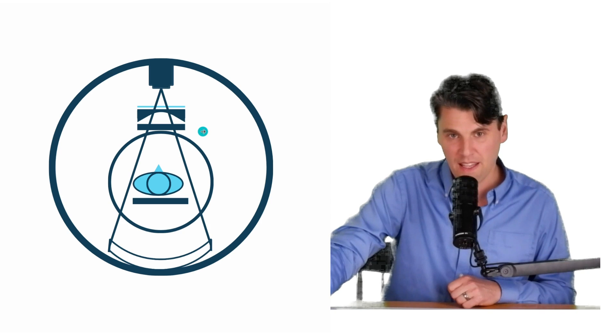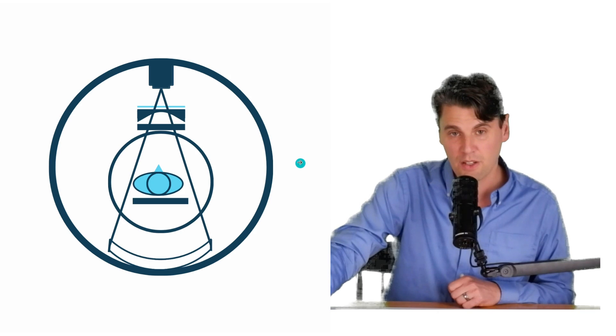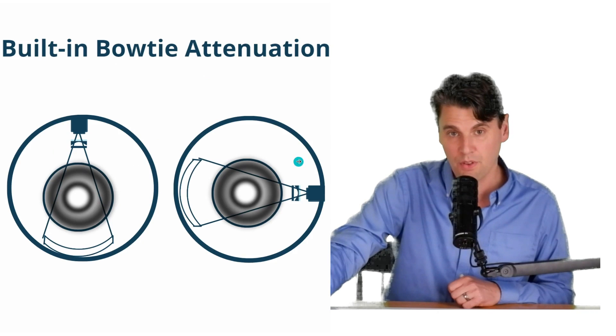This is the bowtie filter right here on our system, and your patient's down here. And again, this is going to rotate around, right? The whole thing, except for the patient, is going to be rotating around on the gantry. So I'm going to show just a couple of different views of that.